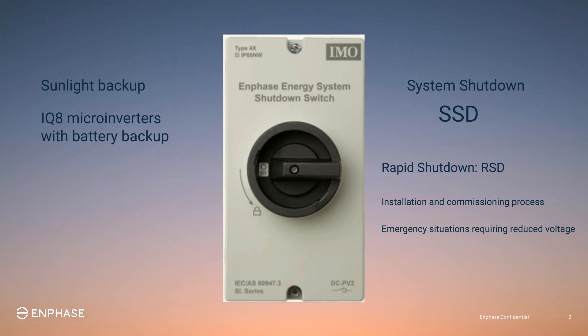If an IQ system controller is stuck in an SSD state, the home will lose all power until the issue is resolved. As you begin troubleshooting, remember to take pictures of all of the steps you take, including multimeter readings with the probes on the test points.